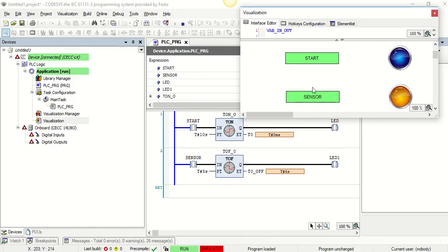So understanding that in a bit more detail really adds value to your coding, and you can create much more powerful things because you can use these in very sophisticated ways. Now, we've also covered in videos that essentially a TON, we can arrange it in a particular way to become a TOF anyway. I tend not to use TOFs a huge amount just for this reason, that it always is on the falling edge, which may not be ideal, because if a button gets stuck in real life, or if a sensor is left on, or triggered on and not come off, it can be a wee bit awkward. But there definitely is a place for them, and I definitely do use them.